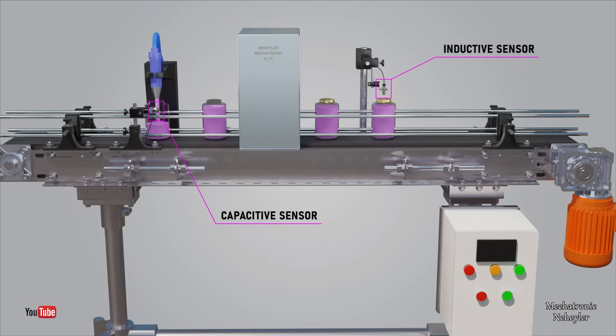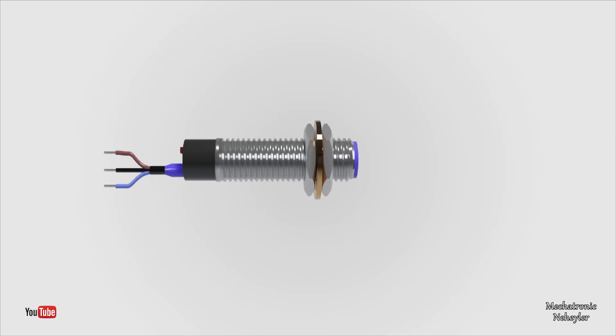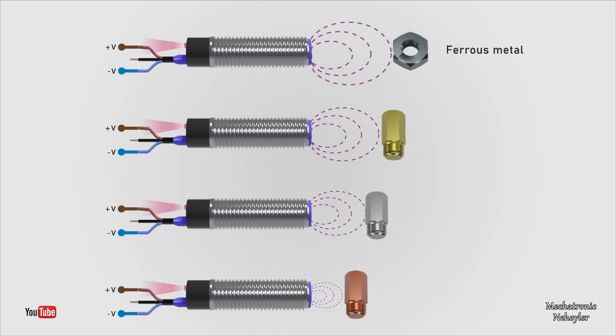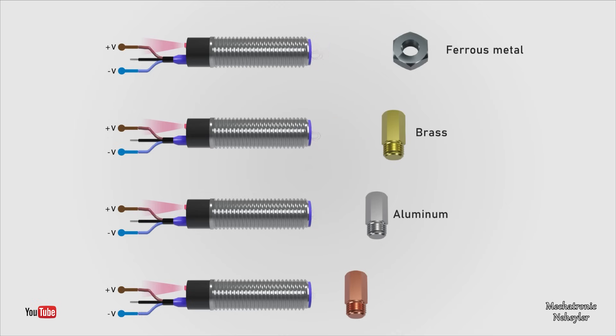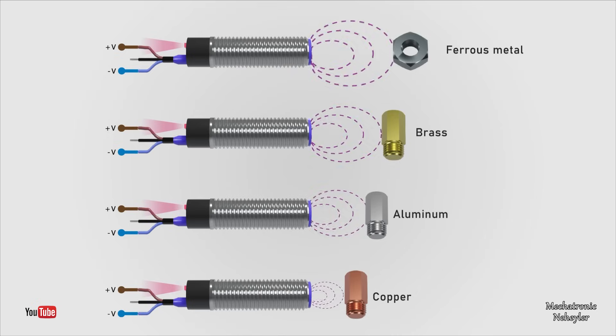Firstly, let's see about the inductive proximity sensor. An inductive sensor is an electronic device that can detect ferrous metal objects at a given distance without physical contact. Some inductive sensors can also detect non-ferrous metal objects such as brass, aluminum, and copper, although the detection range on non-ferrous material decreases. The sensing distance depending on the material can be found in the datasheet of the sensor, though this distance is not more than 80 millimeters.